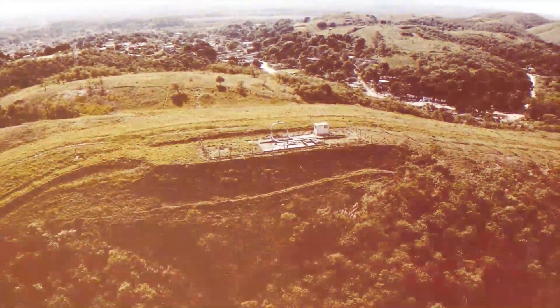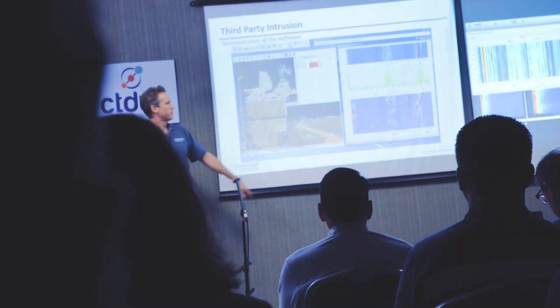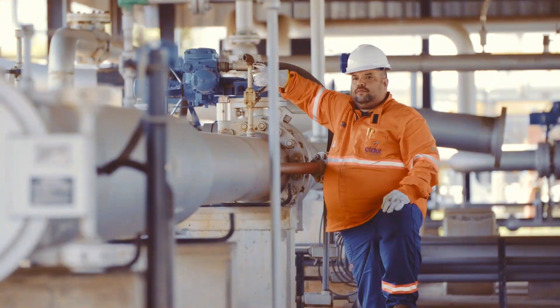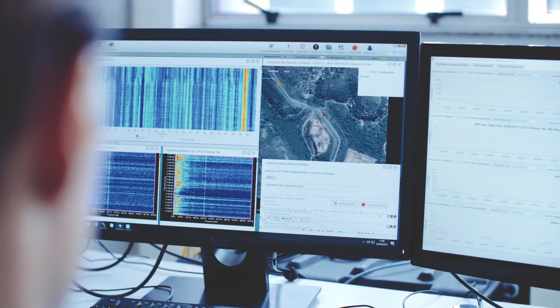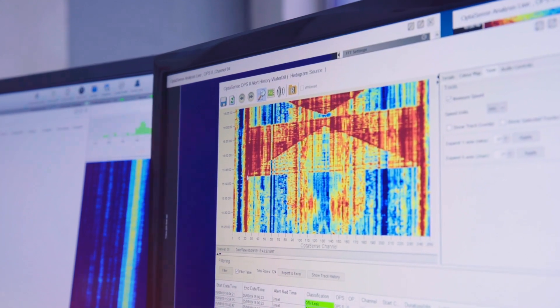Simulating a realistic leak event is difficult in itself. In order to build confidence in our system, we want to simulate multiple leak events to provide confidence through statistics. In total between the two sessions, we've tested about 30 different leaks of different sizes, ranging from small leaks of around 15 litres per minute up to the largest, which was approximately 300 litres per minute.